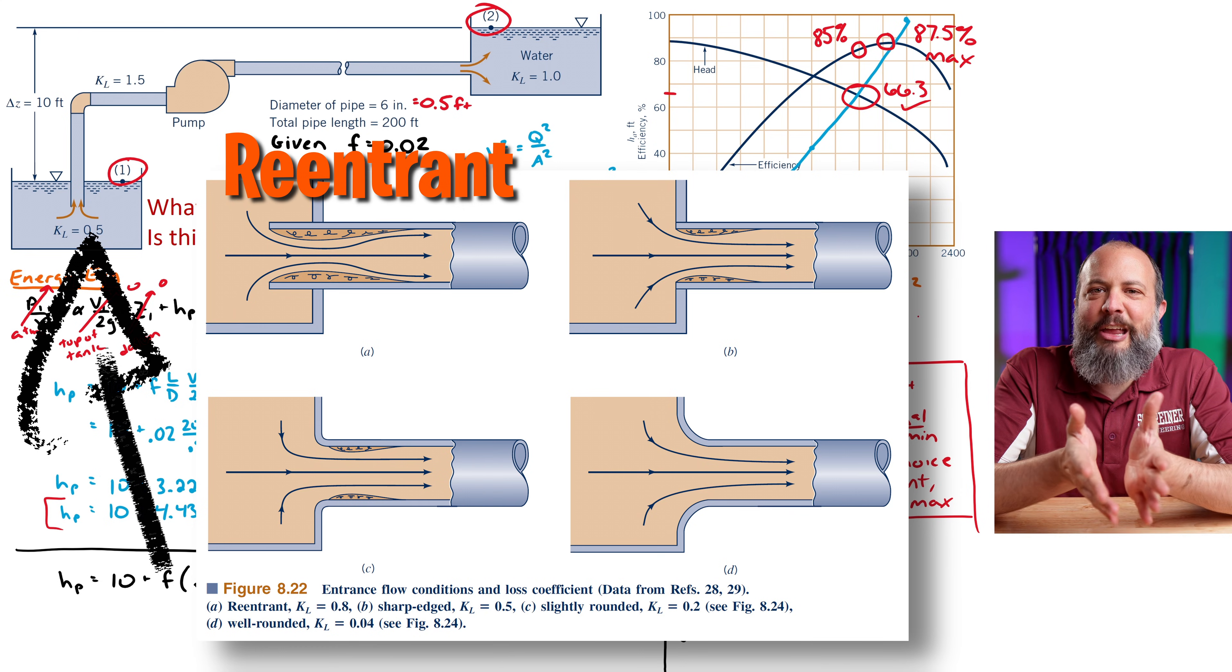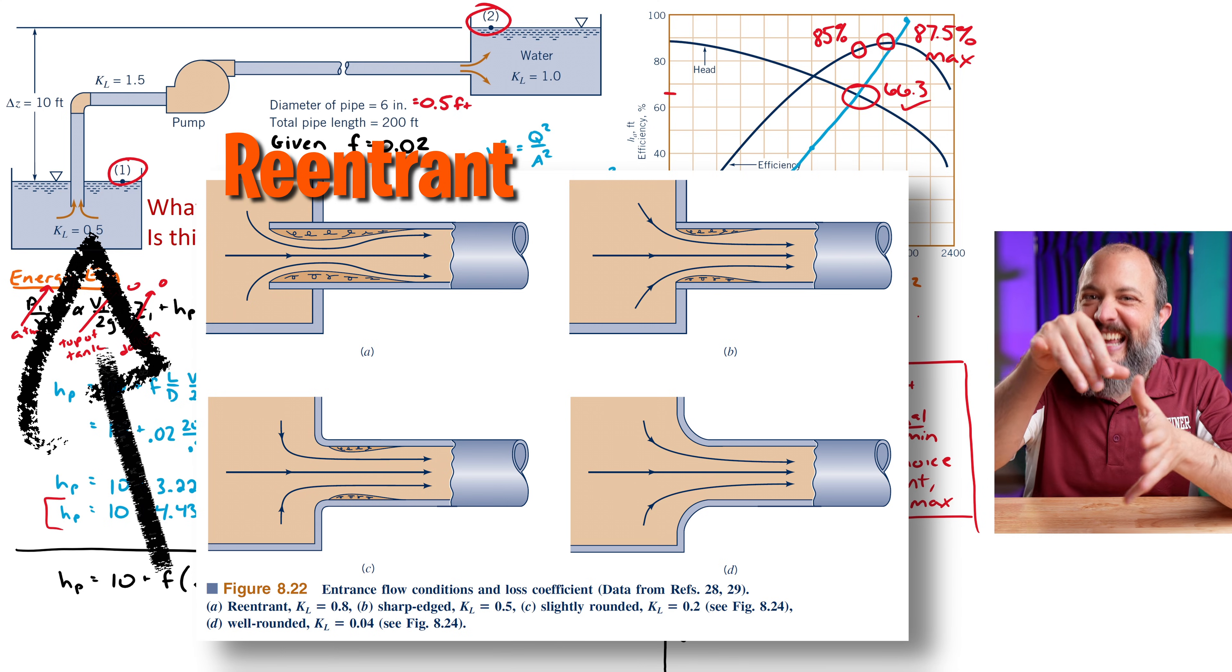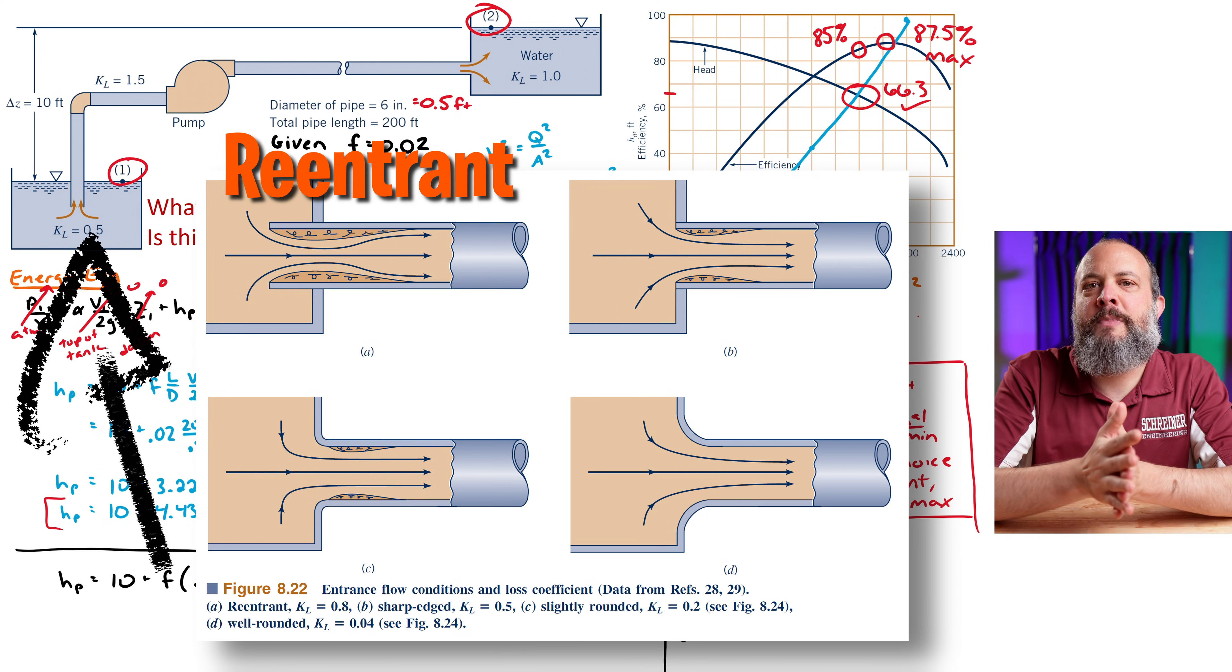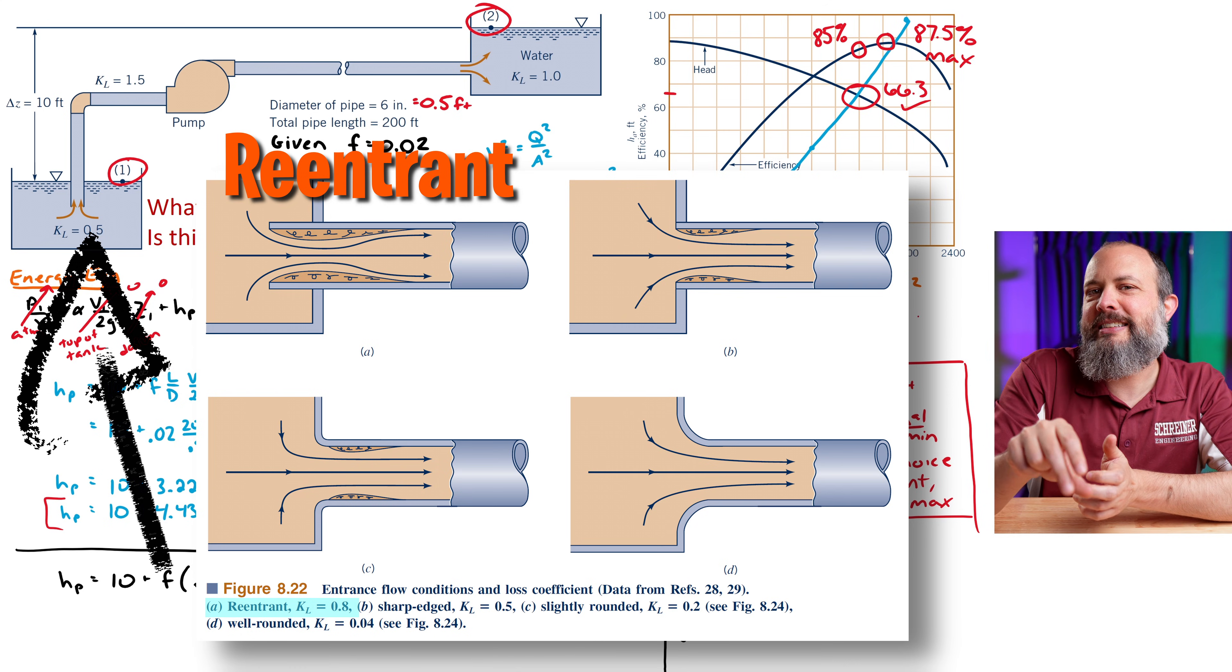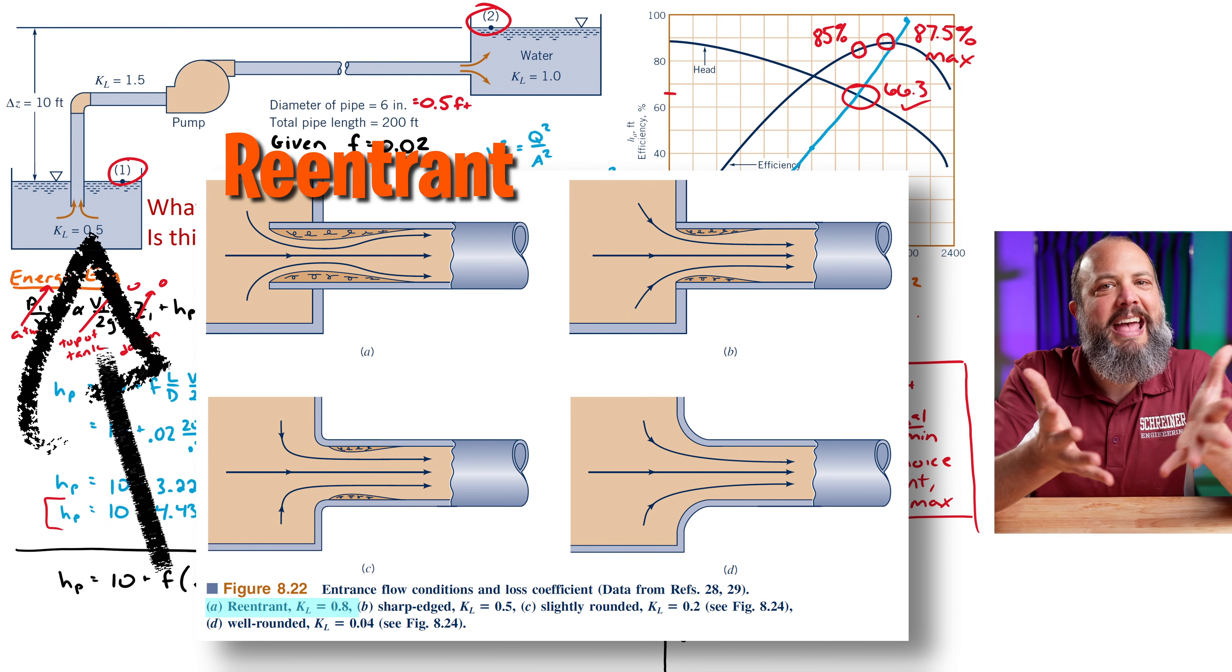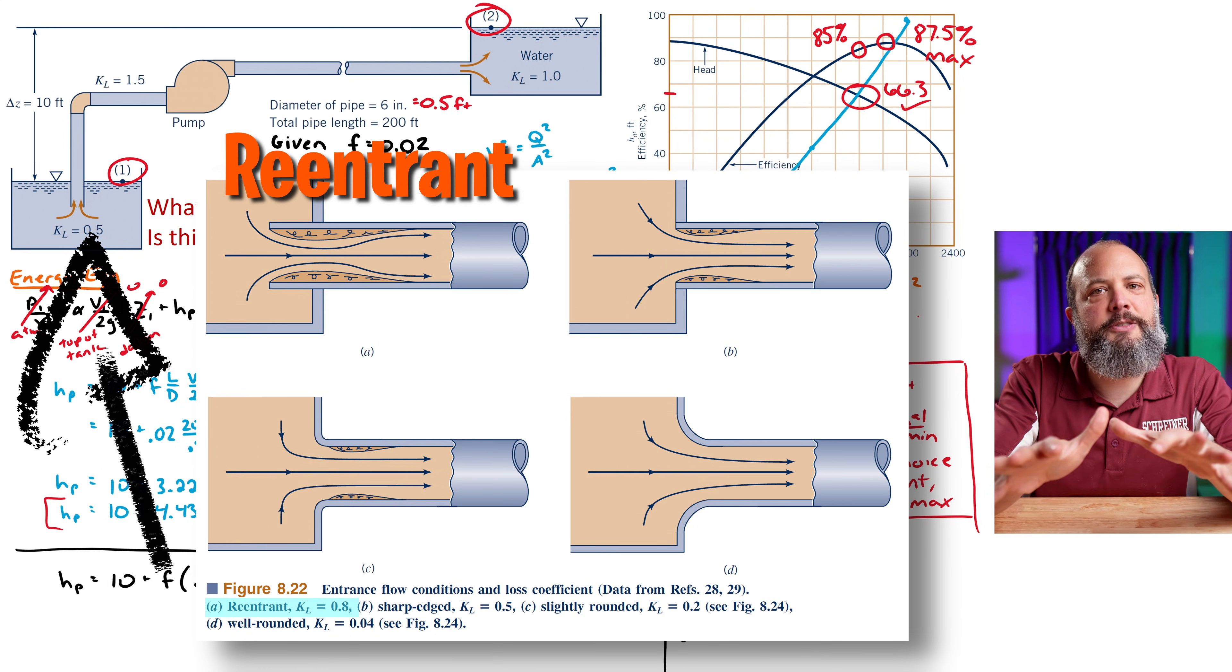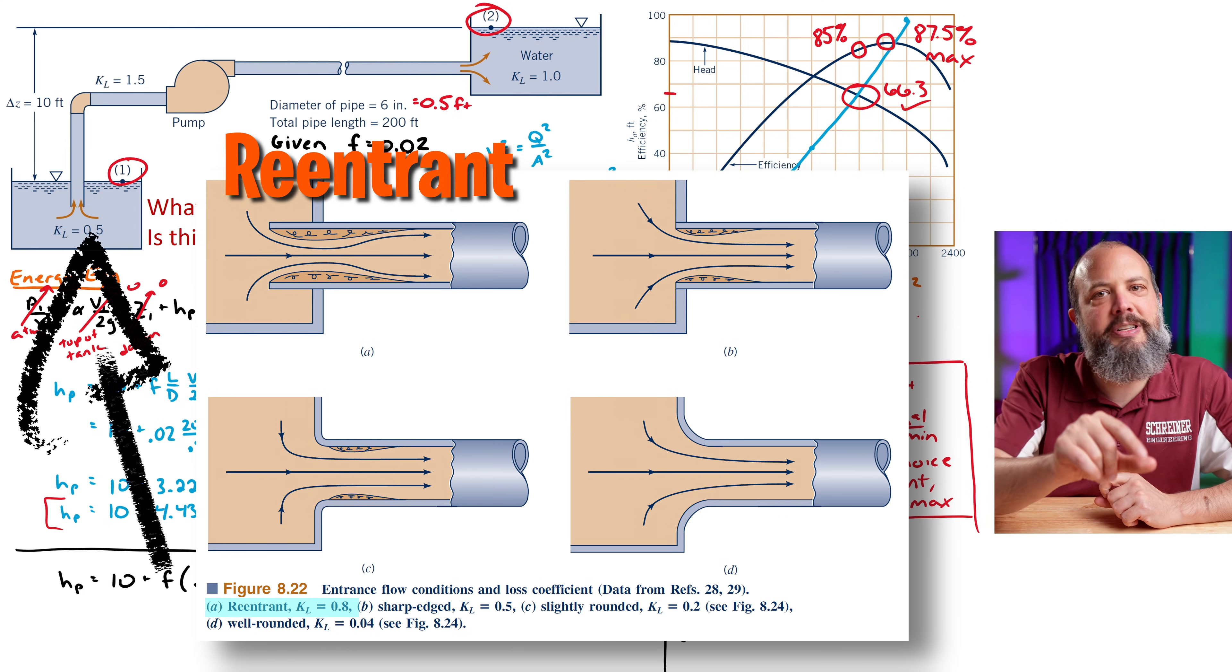So looking at this picture, this looks like a re-entrant entrance. That's where the pipe is actually sticking into the tank. That's called a re-entrant. And in my table, this would have a K value of 0.8, not 0.5. 0.5 would refer to a regular square edged entrance. And even checking different textbooks, they were all kind of the same number. So I'm going to use 0.8 for the entrance instead of the loss of 0.5 that shows on the picture.